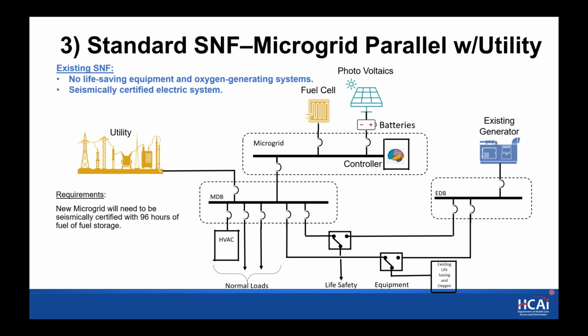So in this case, the existing generator would remain as is. That would fulfill the requirements for the emergency generator to back up the code mandated emergency loads, and the microgrid would back up the entire system, which would fulfill the requirement to back up the new loads introduced by AB 2511. I think we can move to the next one.